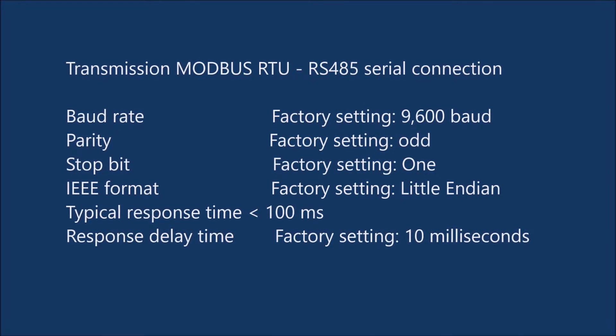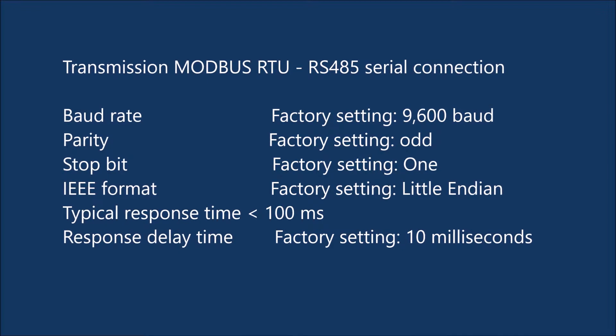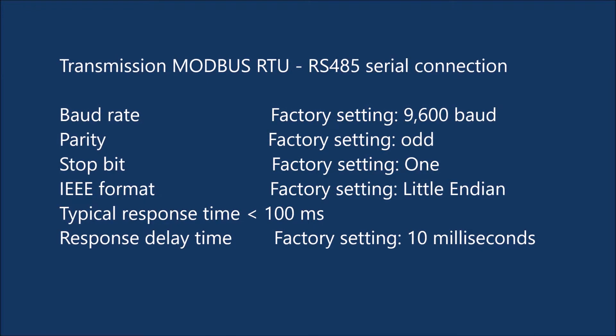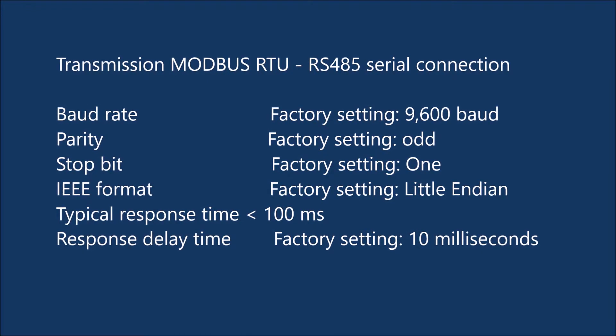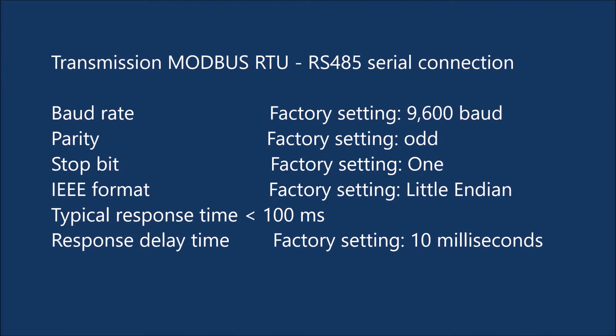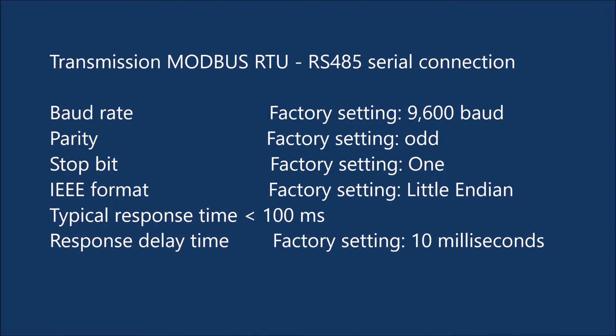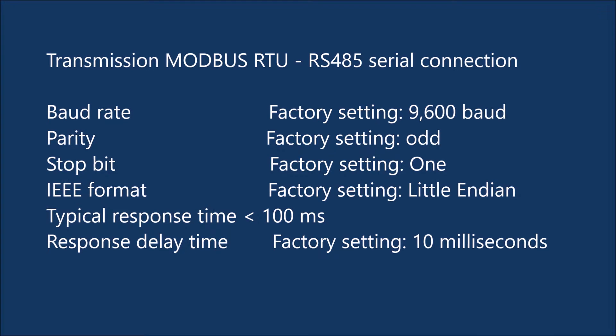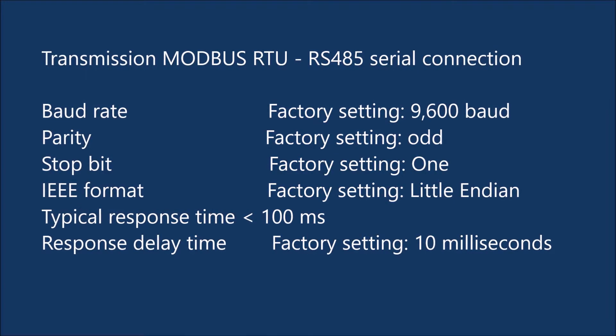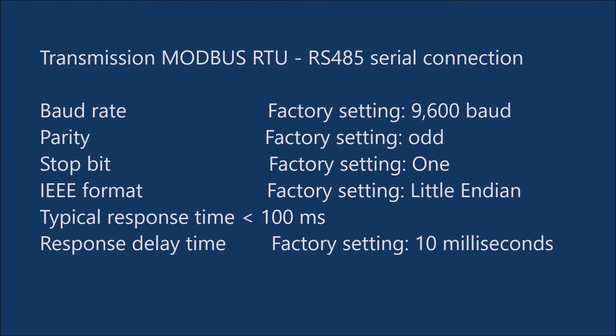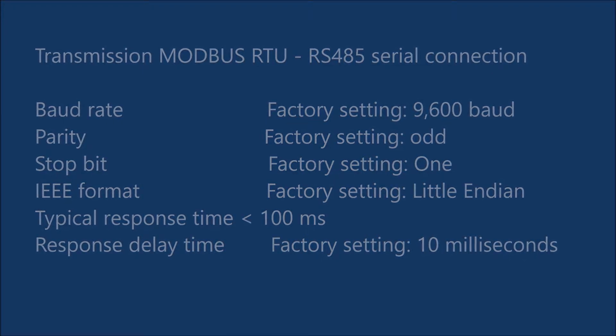Parity factory setting: odd. Stop bit factory setting: 1. IEEE format factory setting: little endian. Typical response time: less than 100 milliseconds. Response delay time factory setting: 10 milliseconds.